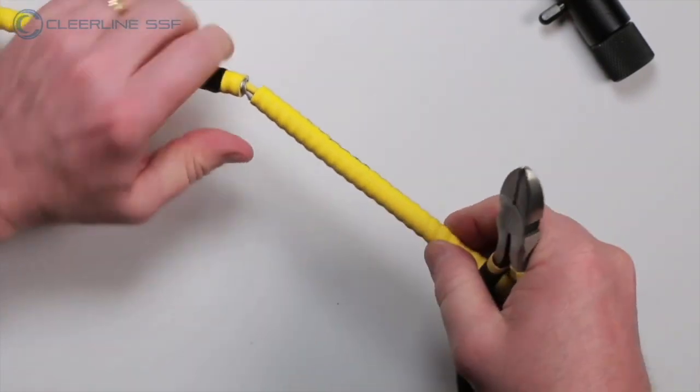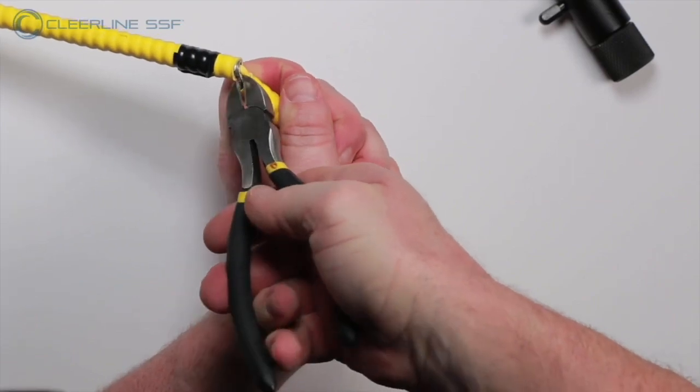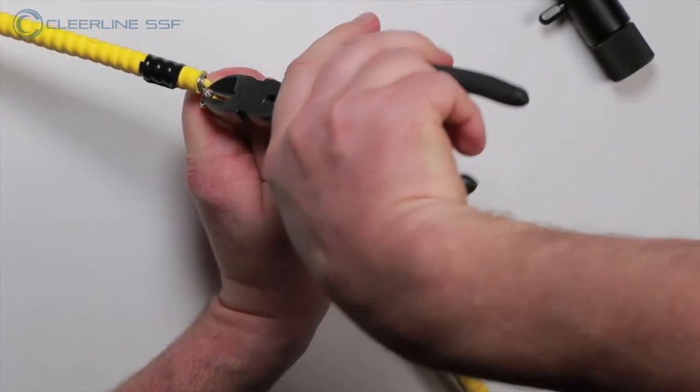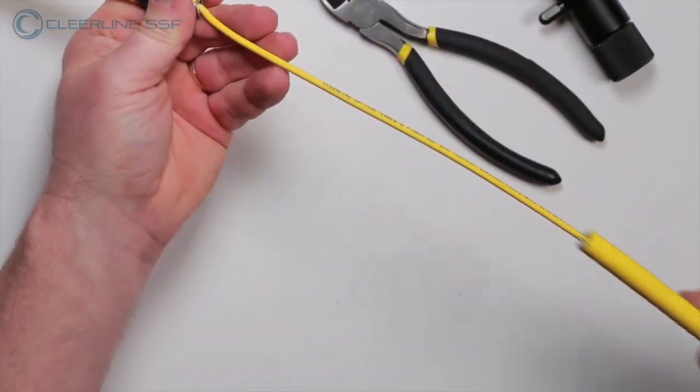Electrical tape can be applied for protection of the sharp edge if needed. If installing a grounding lug or bonding strap, perform a longitudinal cut and ring cut with the slitting tool such that you only remove enough of the PVC layer on the armor for grounding.